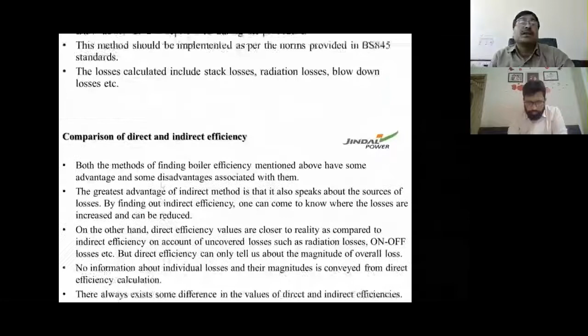If you compare direct and indirect efficiencies, the methods of finding boiler efficiency mentioned above have some advantages and some disadvantages. The greatest advantage of the indirect method is that it also speaks about the sources of losses. By finding out indirect efficiency, one can come to know where the losses are increased and this can be reduced. On the other hand, direct efficiency values are closer to reality as compared to indirect efficiency on account of uncovered losses. What happens is that in indirect efficiency, some losses we cannot calculate.